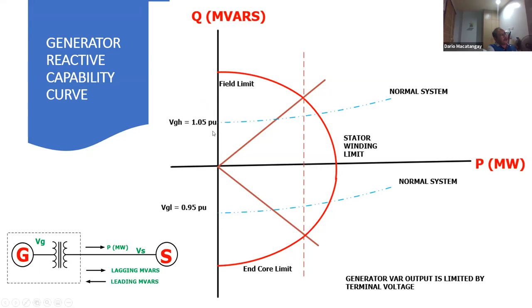Now you can see here that if you keep on increasing the voltage, this area here is already very high voltage. And you are subjecting the generator to insulation stress. If you are increasing the voltage here, let's say you're going to 120%, and your generator is 13.8 kV, times 1.2 is actually 16.56 kV, 16,560 volts. You don't want the generator to operate at that value for a long time. You need to trip it. You cannot operate at that. This is too high. So what I'm saying is that typically the generator megavar output is limited by the terminal voltage, not the generator megawatt output.